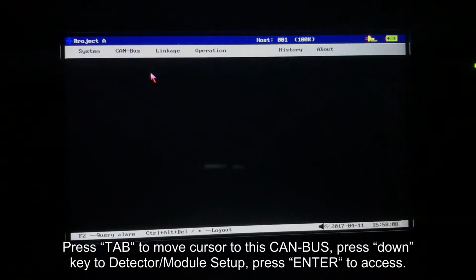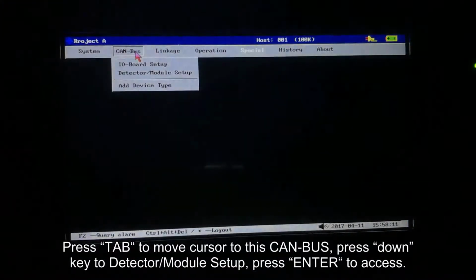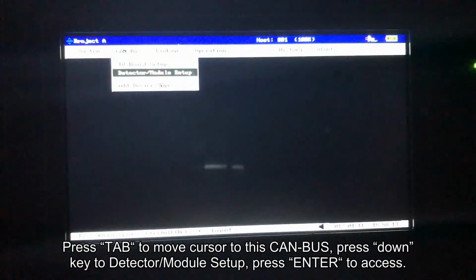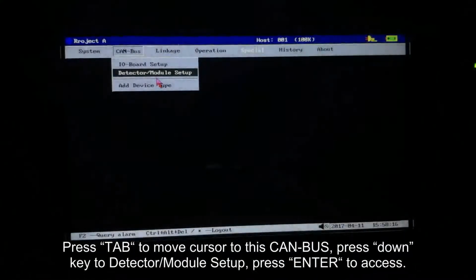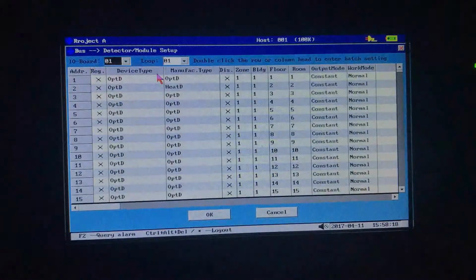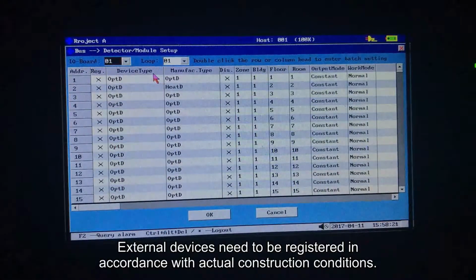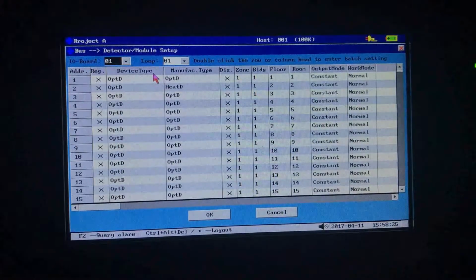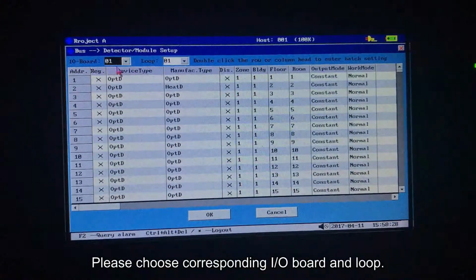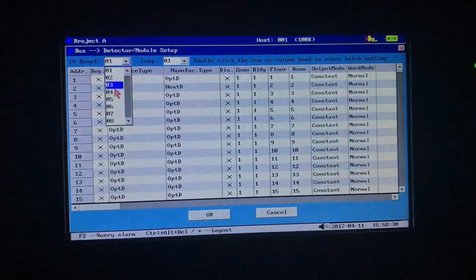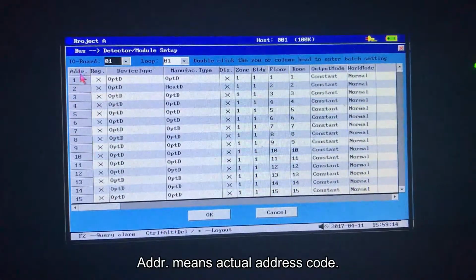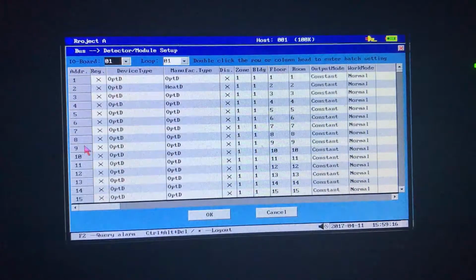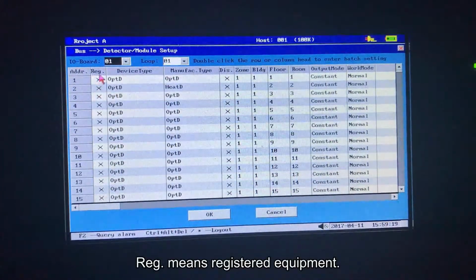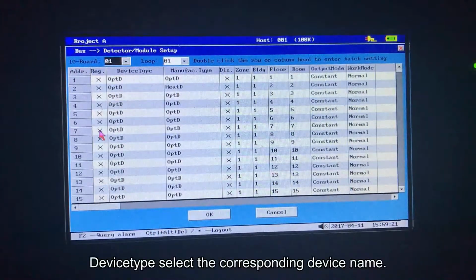Press Tab to move cursor to this CAN-BUS. Press down key to detector and module setup. Press Enter to access. External devices need to be registered in accordance with actual construction conditions. Please choose corresponding I/O board and loop. ADDR means actual address code. REG means registered equipment. Device type, select the corresponding device name.